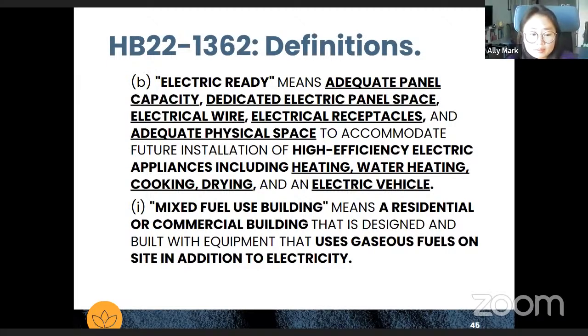Rob? I suppose it's immaterial at this point in time, but I'm a little concerned with the definition of electric ready, insofar as a home that's just built to code, I don't think is electric ready. I just did some napkin calculations, so take them for what they were, but a home with a 60,000 BTU heat load would require 17 kilowatts of peak electric load for equivalent capacity. That's 71 amps, that's a lot of power, assuming a 240 volt connection. So when we start talking about adequate panel capacity, those numbers are going to start climbing really fast.